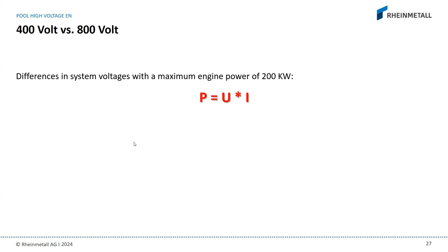The difference between the systems can be calculated for a 200 kilowatt engine, a normal range engine. Using the formula power equals intensity by tension, with 200,000 watts we get 500 amps at 400 volts. Doing the same calculation at 800 volts with 200,000 watts, we get 250 amps. Now we might say that's good because higher voltage lets us use smaller cable diameters, but that's not the real reason.